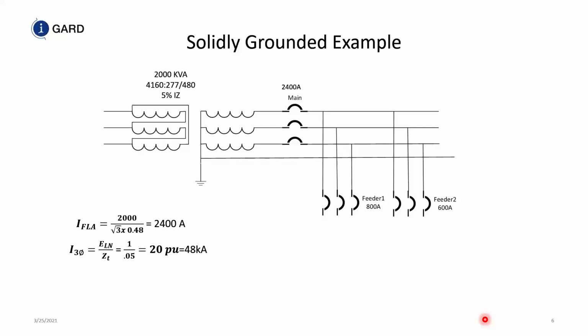in this particular example, a 2000 kVA transformer, 5 kV primary, and for this one I use a 277/480 volt secondary. So you can see we have a 2400 amp full load current on the system, so we have a 2400 amp main breaker. We have two particular feeder breakers in this scenario, 800 amp and 600 amp. There could be more. This is just showing part of the circuit. The three-phase bolted fault current on this, using a strict rule of thumb, is going to be around 48,000 amps. So if you have a full three-phase bolted fault current, you can get as high as 48,000 amps.